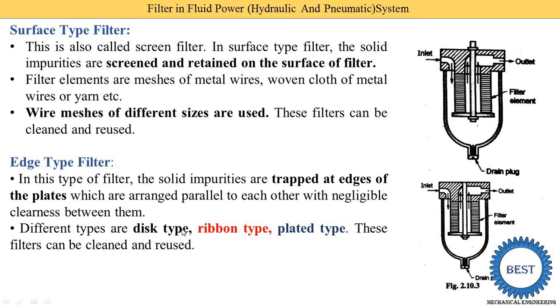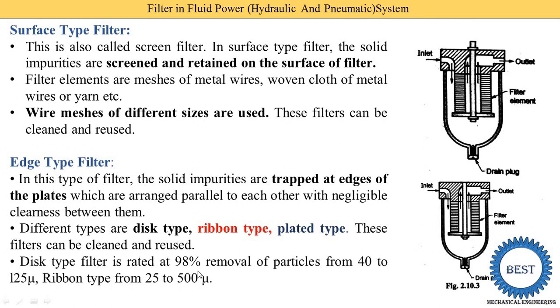Disc type filter elements are cylindrical components rated at 98% removal of particles from 40 to 125 microns. Ribbon type filters remove particles from 25 to 500 microns. So ribbon type filters handle a wider size range — up to 500 microns on the upper side and 25 microns on the lower side, compared to disc type which ranges from 40 to 125 microns.